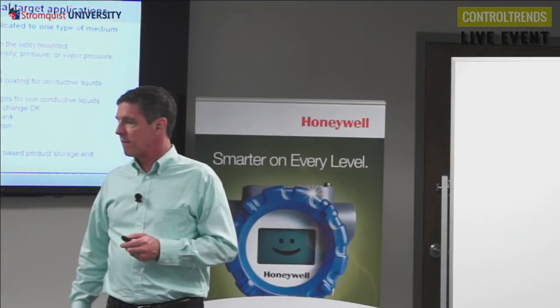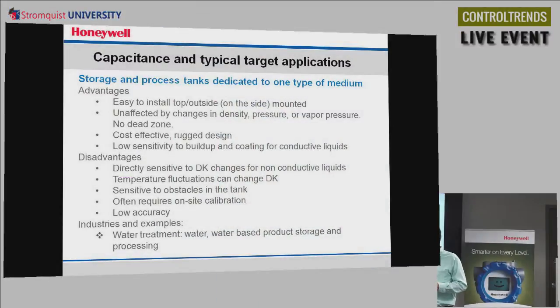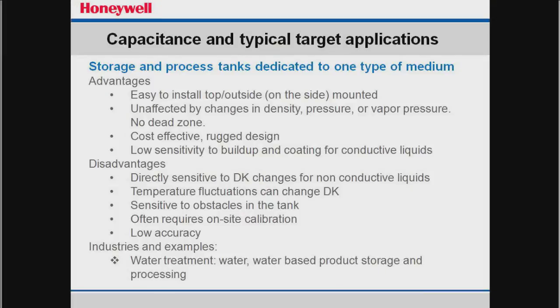So, advantages and disadvantages. Advantages: they're easy to install. They can be mounted on the top or on the outside, and they're not really affected by changes in density or pressure necessarily. They don't really have the dead zone we talked about at the top end of the measurement. They're cost effective, fairly rugged, and they're not real sensitive to buildup and coating for conductive liquids.